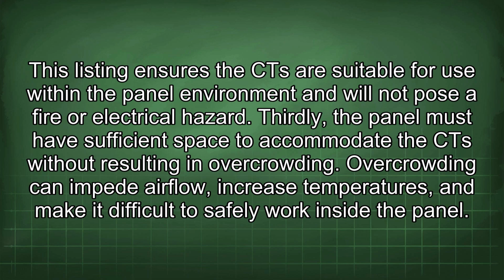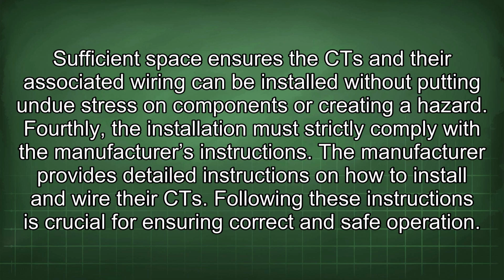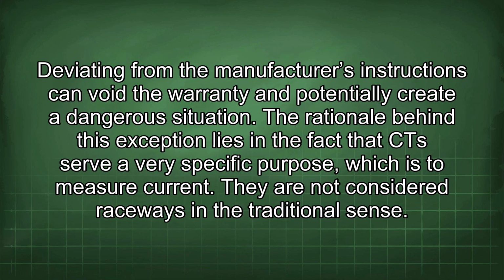Thirdly, the panel must have sufficient space to accommodate the CT without resulting in overcrowding. Overcrowding can impede airflow, increase temperatures, and make it difficult to safely work inside the panel. Sufficient space ensures the CT and their associated wiring can be installed without putting undue stress on components or creating a hazard. Fourthly, the installation must strictly comply with the manufacturer's instructions. The manufacturer provides detailed instructions on how to install and wire their CT. Following these instructions is crucial for ensuring correct and safe operation. Deviating from the manufacturer's instructions can void the warranty and potentially create a dangerous situation.